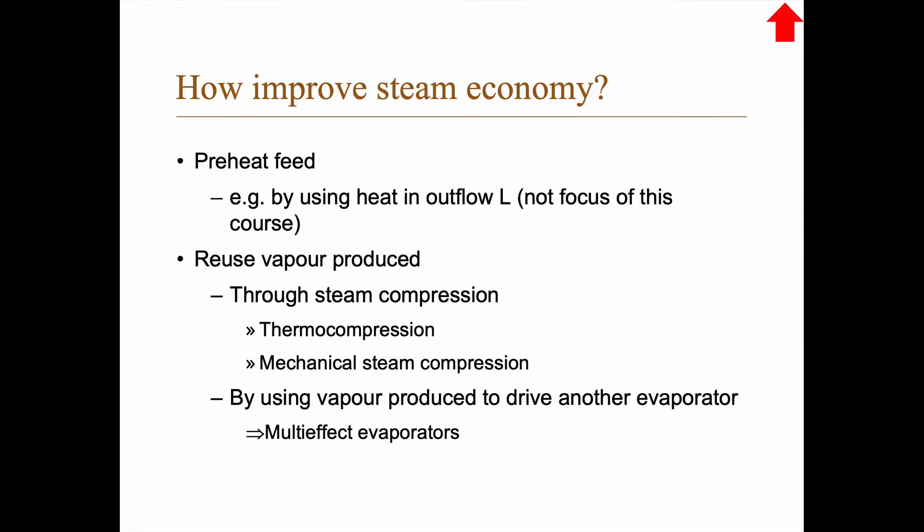So we can improve the steam economy by preheating the feed, by steam compression, but we can also use the vapor produced to drive another evaporator, so have a multi-effect evaporator.